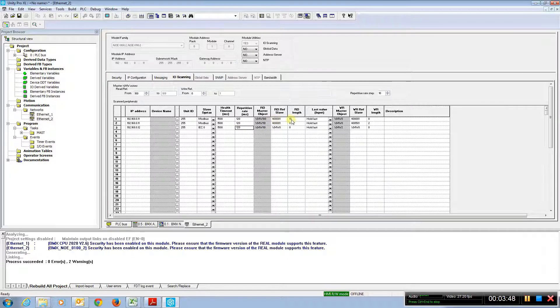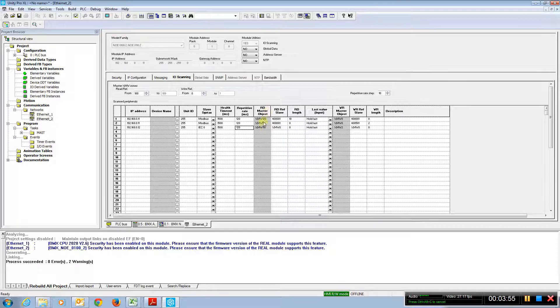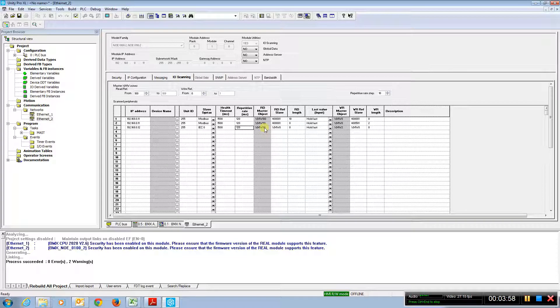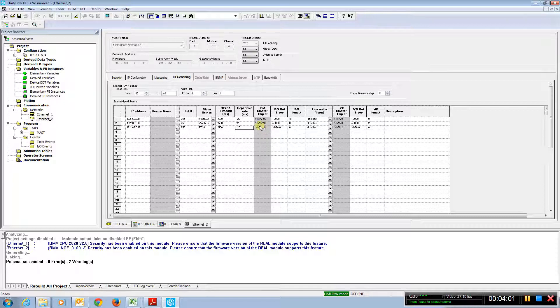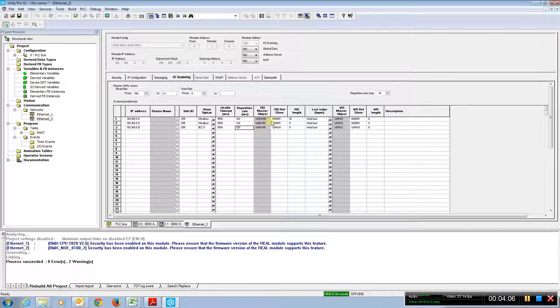We had ten registers, so it automatically put at percent MW110 is the next spot. The reading has to be stuffed in consecutive registers in the M340. In the quantum, you can pick where these specific registers you want to read and store them. But in the M340, they have to be consecutive.